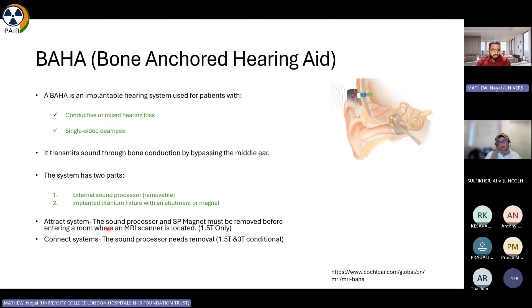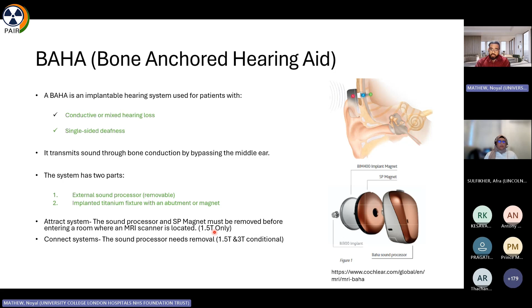If it's an Attract system, this is, by the way, the external component. The Attract system has a sound processor and an SP magnet and must be removed before entering the room. And it's only possible for you to scan it on 1.5T, whereas the Connect system, which looks something like this, can be scanned on a 1.5T and a 3T conditionally. Whereas the Attract system, as the name signifies, has a magnet, and therefore the magnet and the processor need to be removed, and this is only done on a 1.5T. So please go back to Cochlear's website and check which one of these Bahas you've got in front of you before you commence your scan.